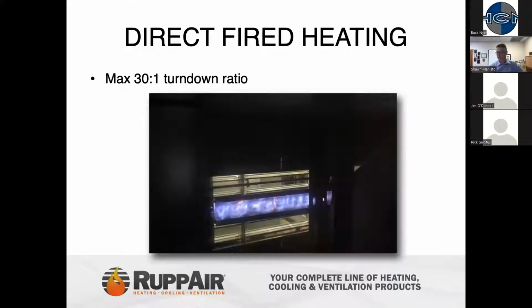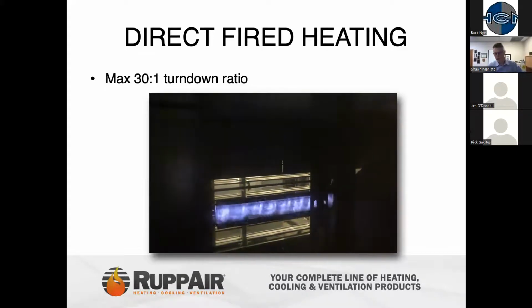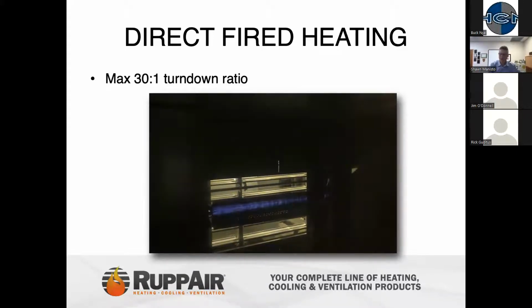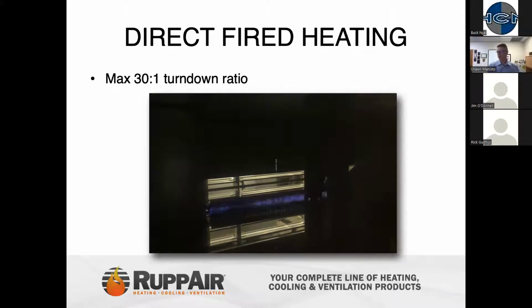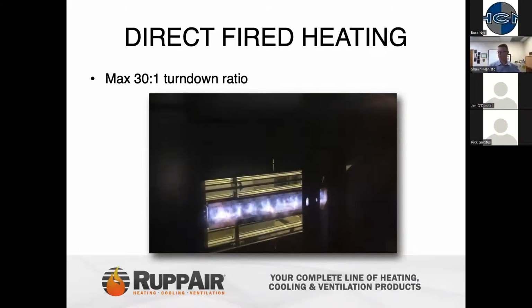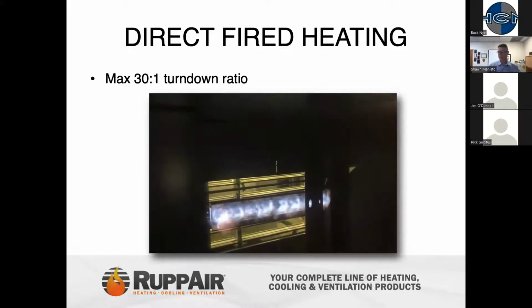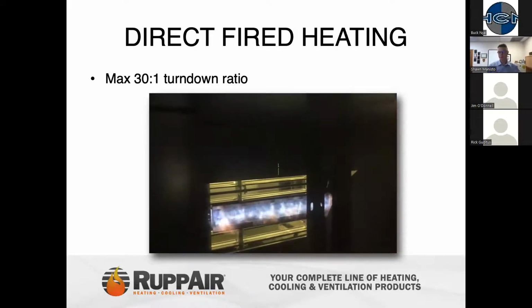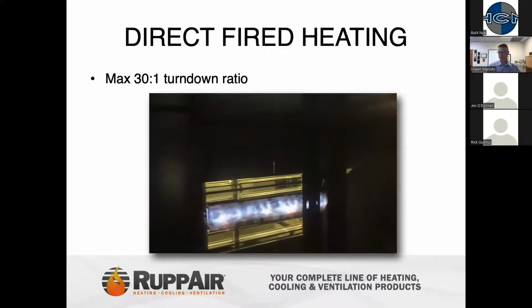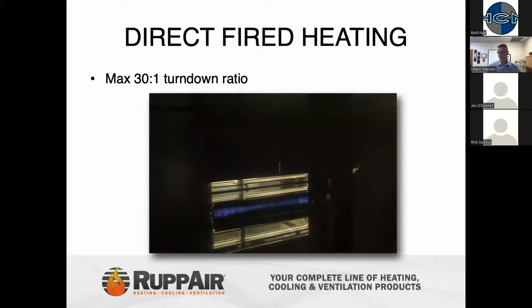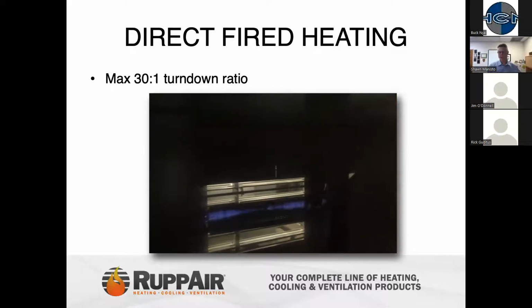This is a nice illustration of how a direct fired unit can modulate. Again, the big benefit of a direct fired system over indirect fired is having a high turn down ratio. Most direct fired units will have a 30-to-1 turn down ratio burner. Even though a burner can have a 30-to-1 turn down ratio, in a true application you're going to come across about a 20-to-1 turn down ratio when properly applied on a direct fired unit. You can see this burner modulating from high fire down to low fire.